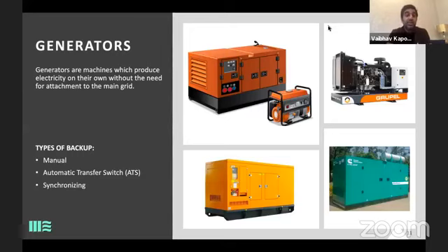In synchronization, there is no delay of power. If something goes wrong, there is no delay you're going to see on site. In automatic transfer switches, there is a delay of minimum 1 second, and you can set it higher. For live events, we usually set it to 1 second, but that is only on the genset side. On site, depending on the equipment you're using, it could show from 3 seconds to anywhere up to 7 seconds for systems to come on.